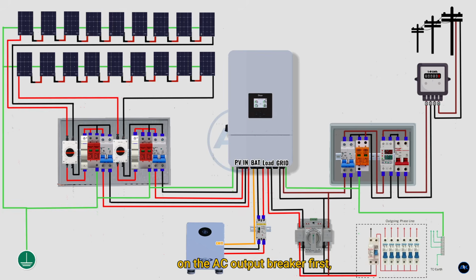Switch on the AC output breaker first, which supplies power to the home's essential load circuits, or the ATS. Then turn on the AC grid input breaker. The inverter will recognize the grid waveform, synchronize, and prepare to operate in hybrid mode. At this point, the inverter should display live data from the battery, PV panels, and the grid.